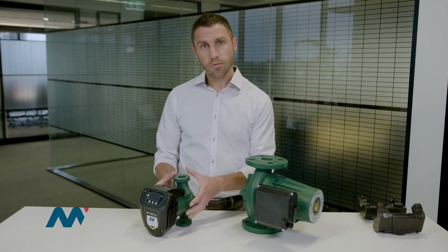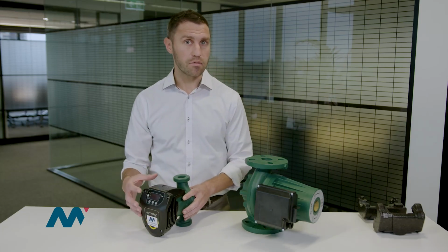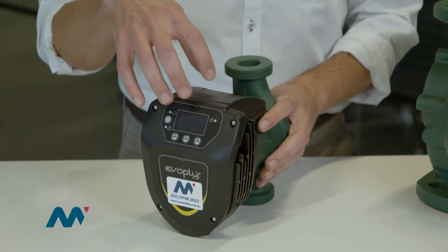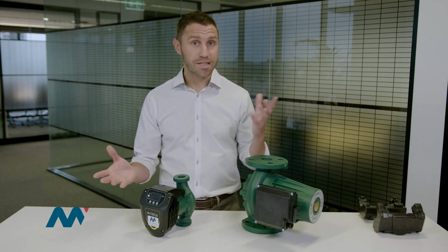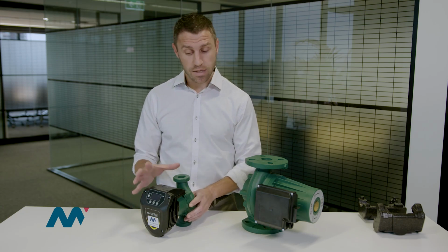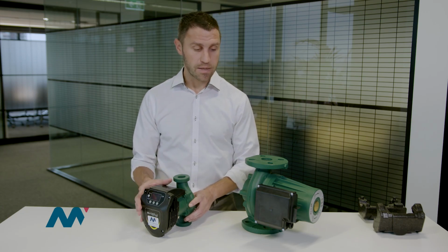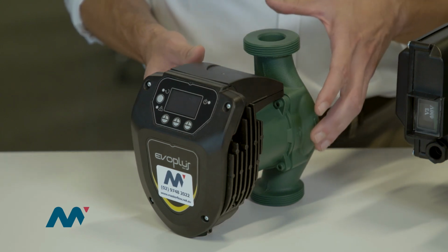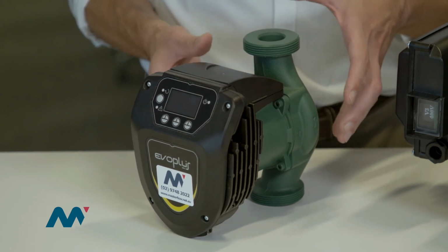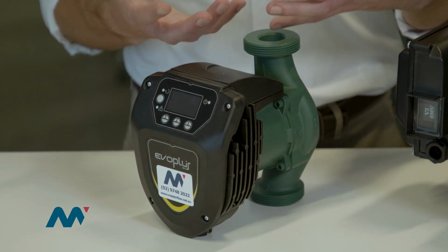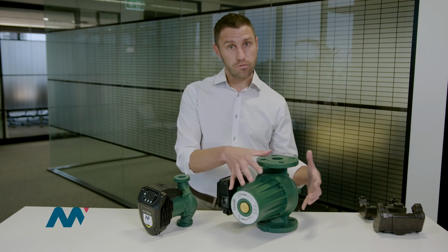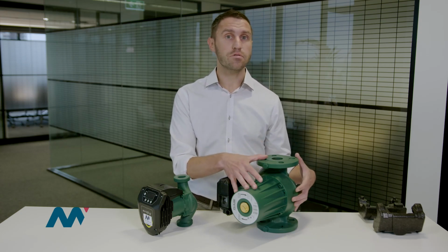In this case, we have an electronic module. So inside here there is an electronic card, and that allows the pump to operate between infinite points of different speed and different duties. So it gives you much more flexibility. Also, the motor is a synchronous motor, also called permanent magnetic motor, that is a better and more sophisticated technology compared to this motor that is an asynchronous motor.